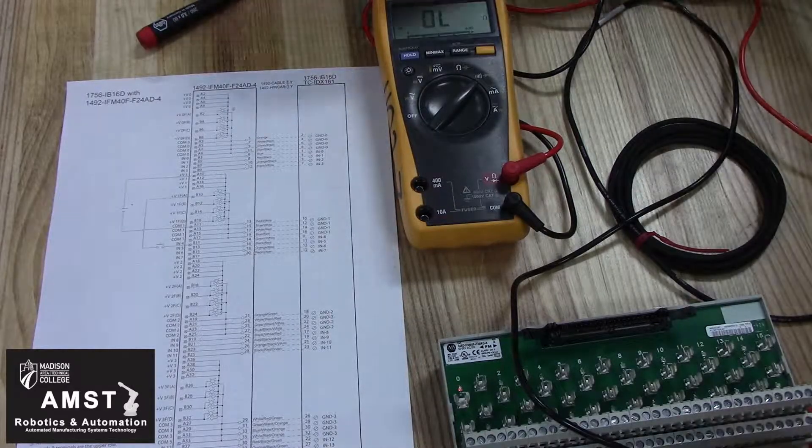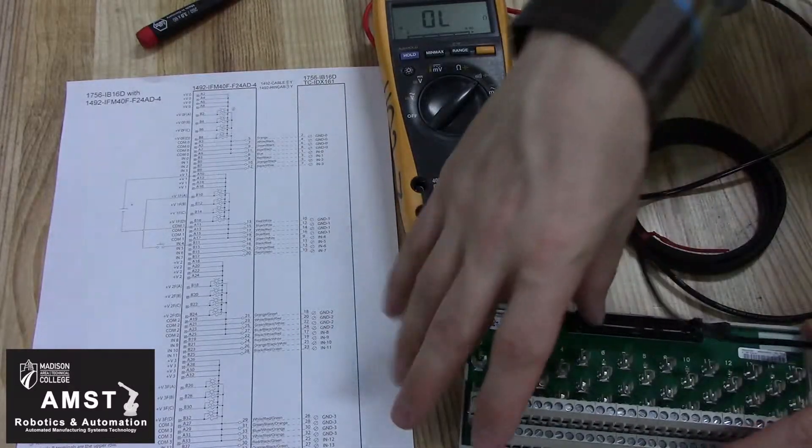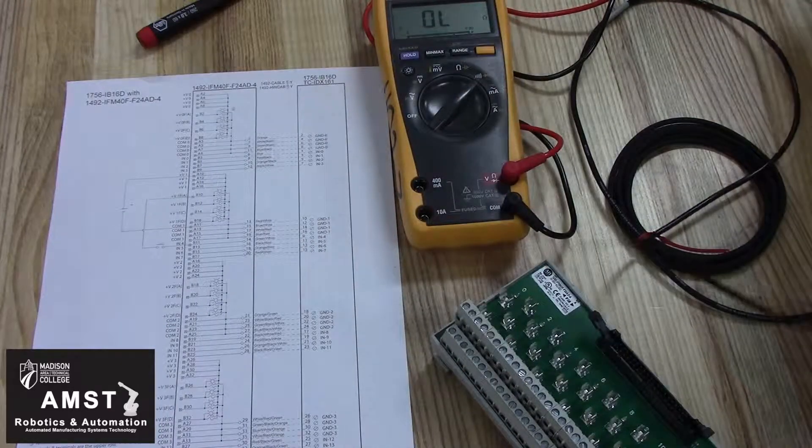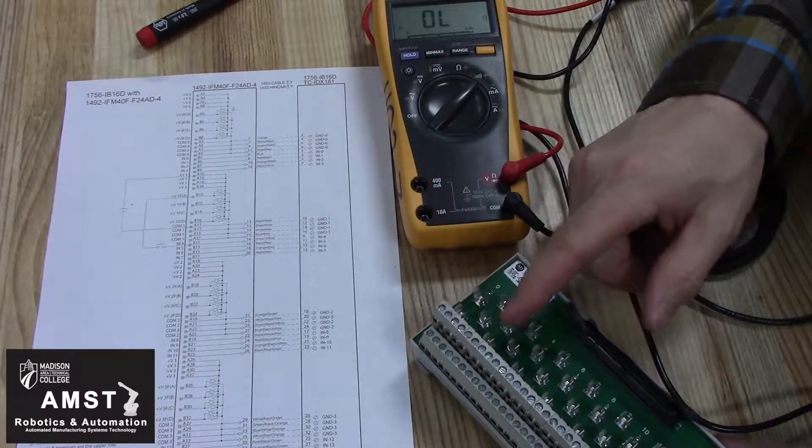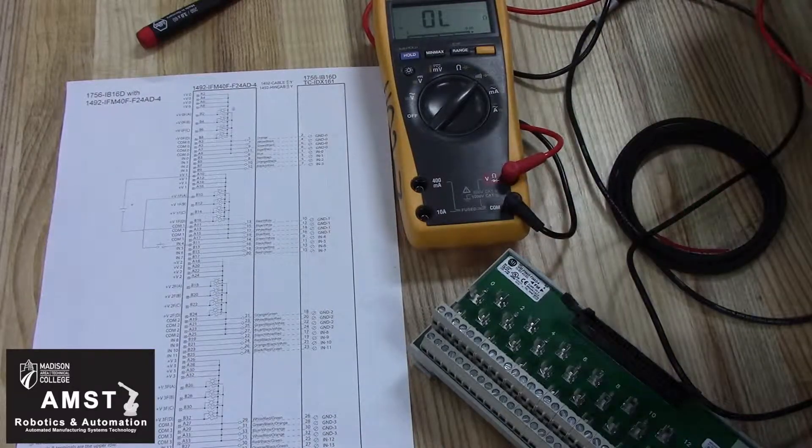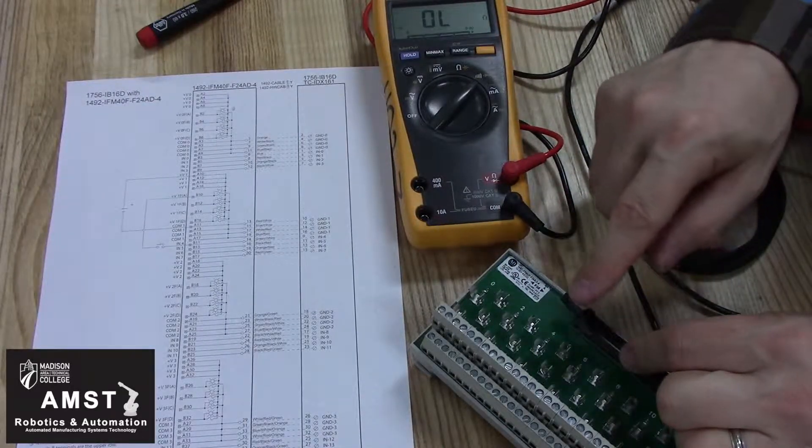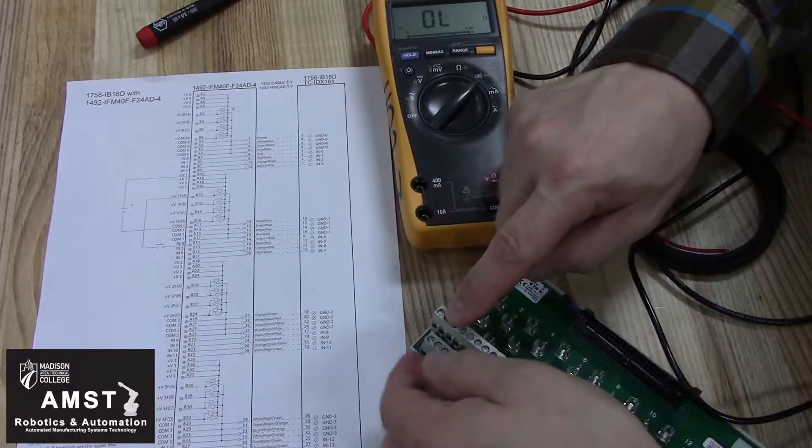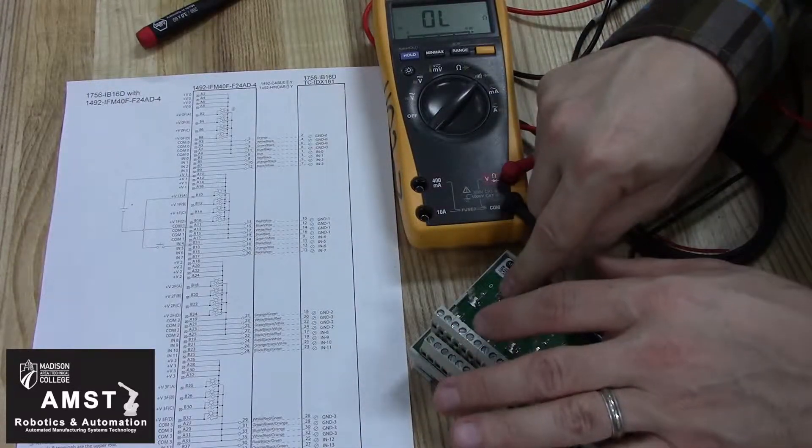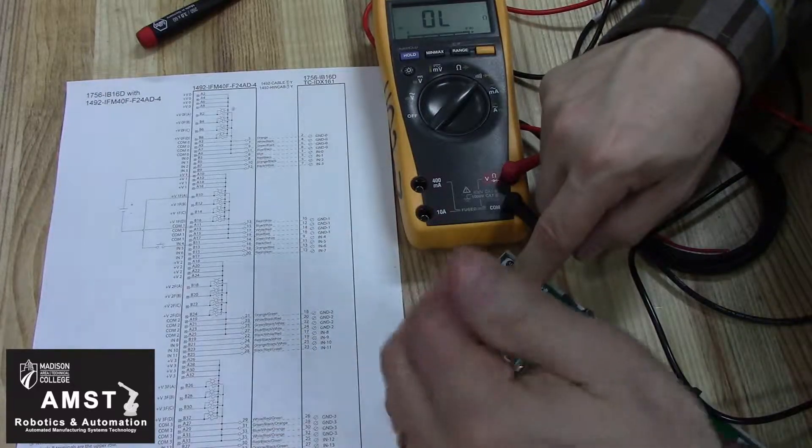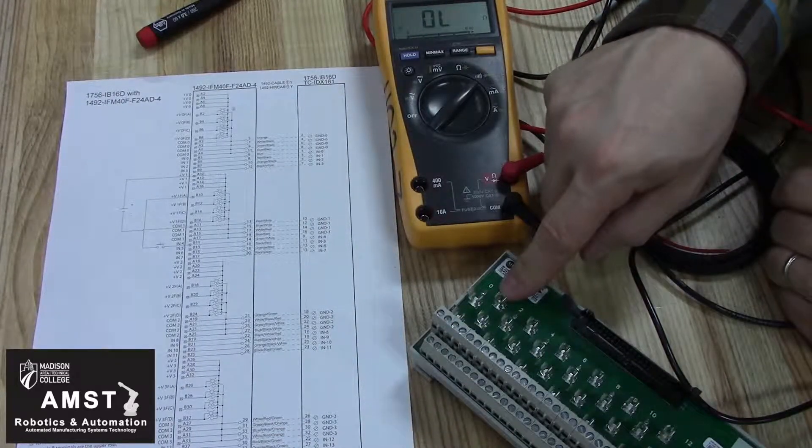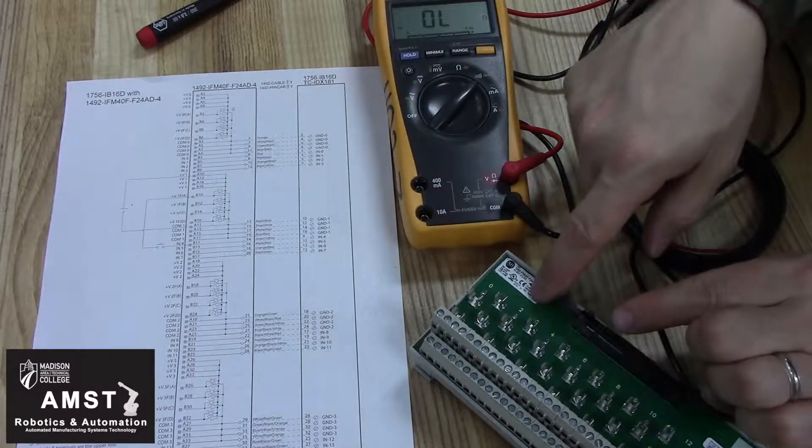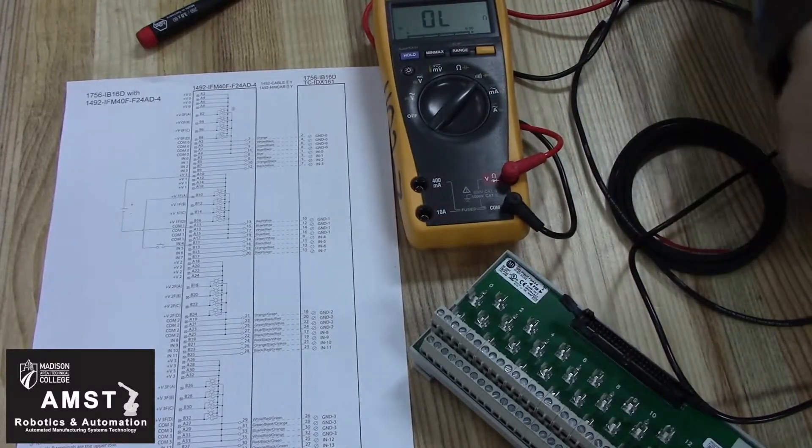So that's your IFM module, Allen Bradley. Each one's specific, and the best way to get familiar with this is actually try and use a continuity tester and pin it out. Understand how these cable connections are connected to your terminals, how your supplies come in and feed the fused, and then fused link feeds your sensor, and your sensor comes back and feeds an input, which connects to an input, feeds to a pin out on your cable, feeding your input module on your PLC.